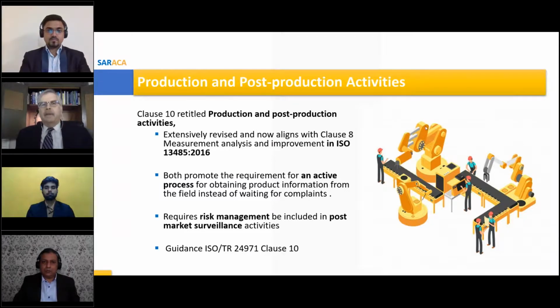If you get something different from what's in your risk management activities, you need to go back to your risk file, look at those differences, update them, and see if you can mitigate the risk that you found. Another method would be to look at your manufacturing process and determine from your product failure analysis on your manufacturing floor whether those relate to any possibilities of failure in the field. You need to review your CAPA findings and determine root cause analysis to a degree that you probably haven't been doing before. And again, you need to look at your audit effectiveness and include that as part of your internal audit. All these facts need to be recorded as part of your post-market surveillance in an active format.